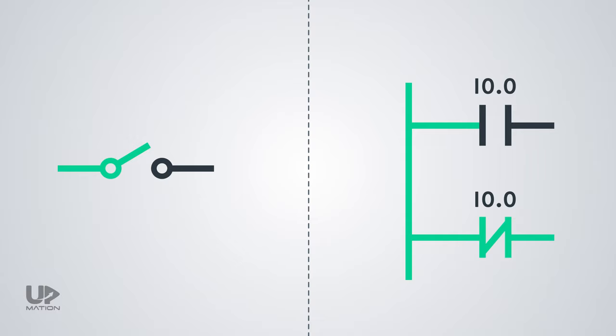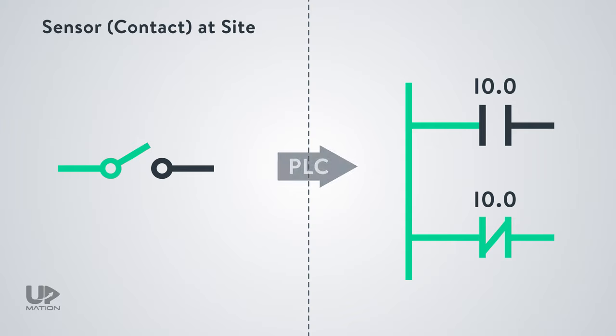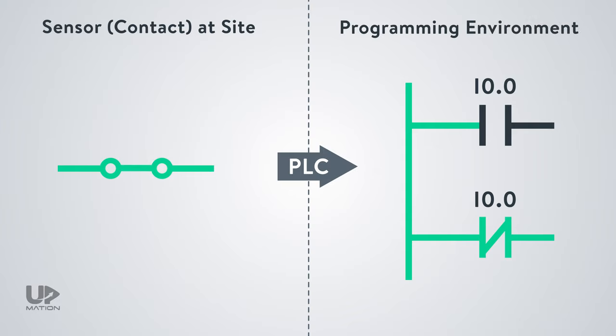There is an important point here. When the actual physical contact is open, the state of its equivalent PLC logic contacts is like this. And when it gets closed, its input to the PLC card, which is I0.0 for example, gets active and their state will be updated like this. So do not confuse the open and closed contacts of the PLC logic with the actual NO and NC contacts.